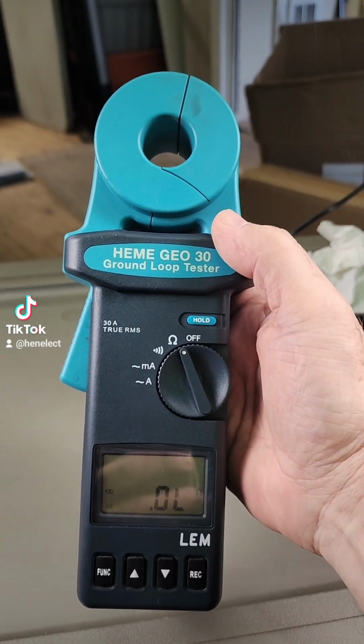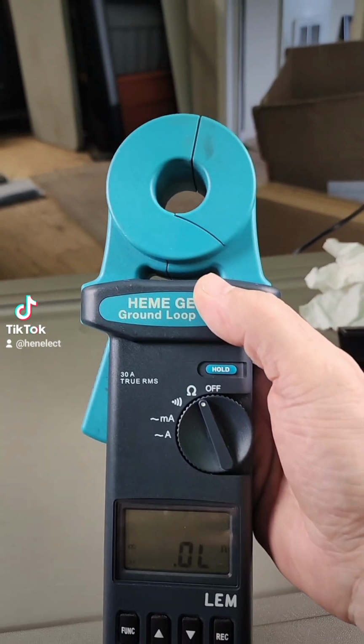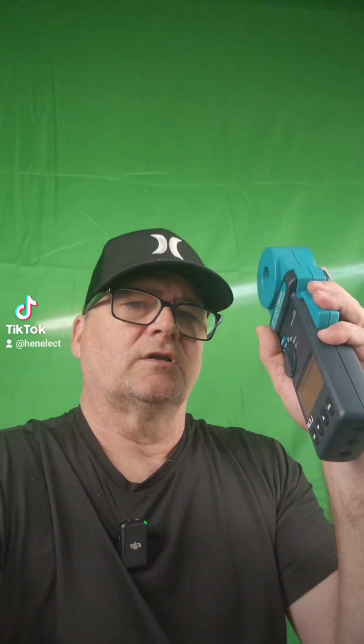So it used to be where the code would say, if your ground rod is 25 ohms or higher, you need to add a second ground rod 6 feet apart, right? Well, no one was buying this. No one was testing this. So the code just says, you know what? Let's just put 2 ground rods everywhere and we'll be done with it, regardless of what the resistance is. And guys, you will be shocked. Only till you have one of these and you play around with this, you'll be shocked, no pun intended.